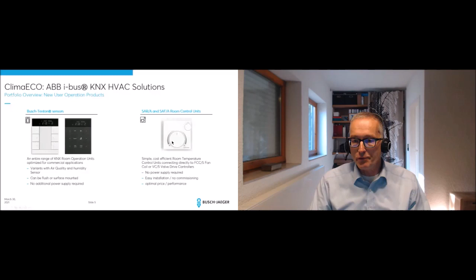So a range of 9 components covers the fan coil control application. Fan coil units are very important in heating and cooling solutions, and we've used these components a lot in the past, but now with a new range offering more functions - for example, we can now also control 0 to 10 volt fans, and simple valve drive control can be used as well. Both components I mentioned have an integrated controller, meaning you can also use components for room temperature control in the room without a controller integrated - simple room temperature measurement is required, and the rest can be done directly in this DIN-rail component.